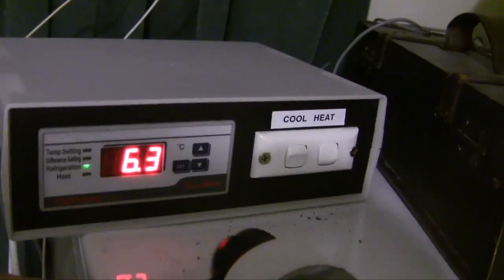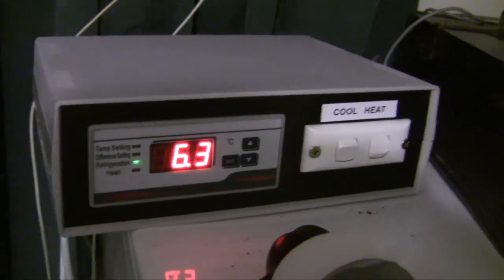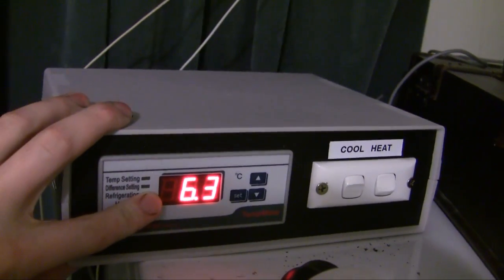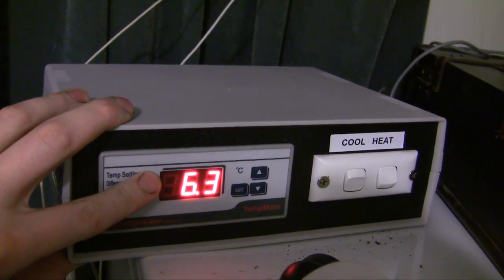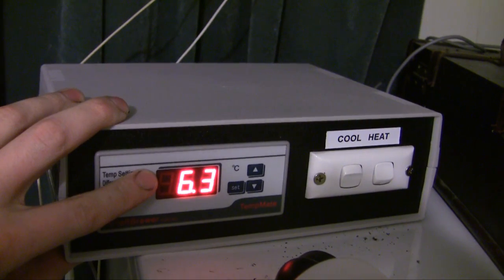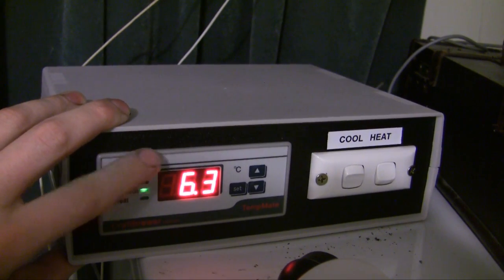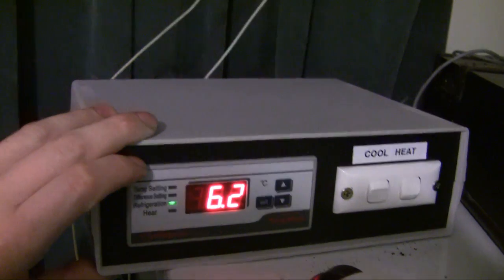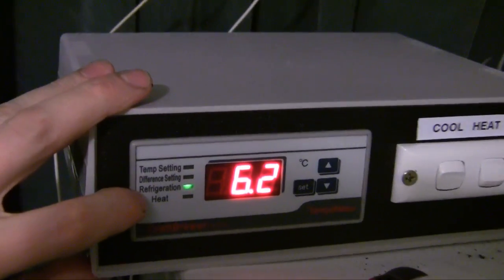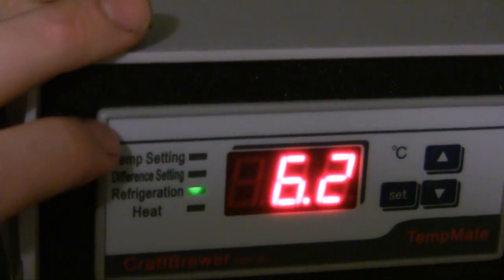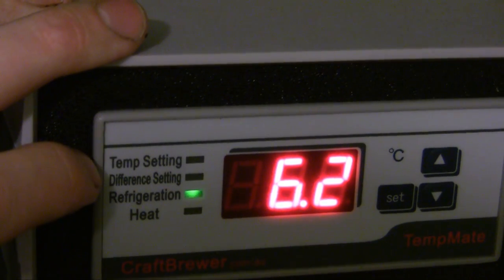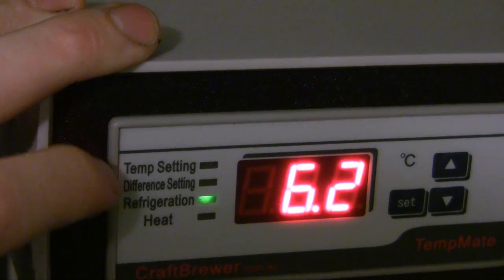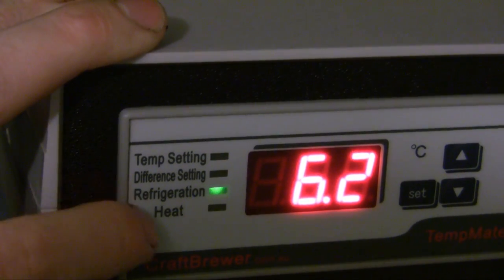It's in a slightly different mode to normal, but I've just made this. Well, I bought this unit probably six months ago, I just never pulled my finger out and put it together. But it's a temperature heating and cooling controller. As you can see here, temp setting - that's what I want - and a differential setting for how high either side of that, whether it's cooling or heating.